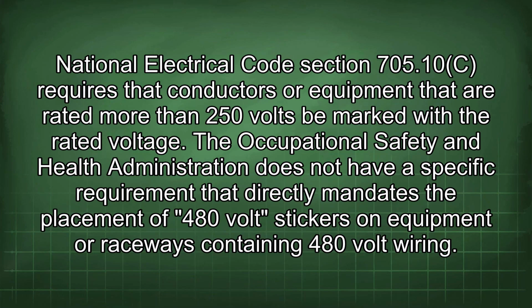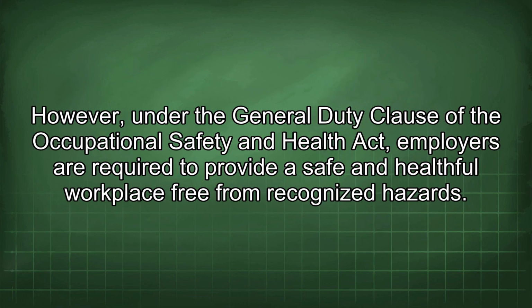National Electrical Code Section 705.10c requires that conductors or equipment that are rated more than 250 volts be marked with the rated voltage. The Occupational Safety and Health Administration does not have a specific requirement that directly mandates the placement of 480-volt stickers on equipment or raceways containing 480-volt wiring. However, under the General Duty Clause of the Occupational Safety and Health Act, employers are required to provide a safe and healthful workplace free from recognized hazards.